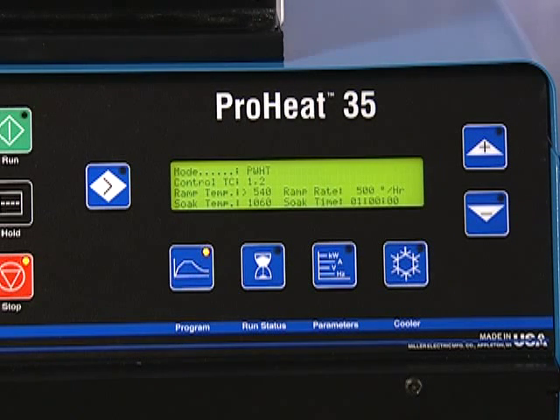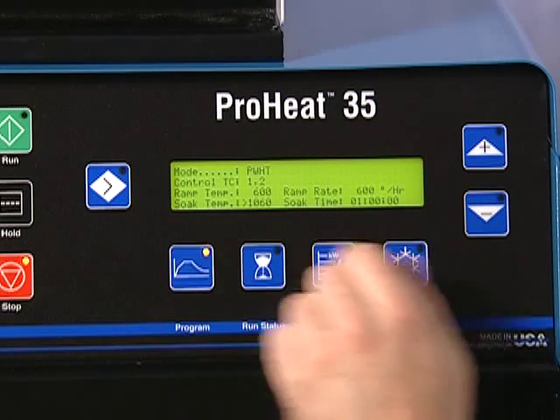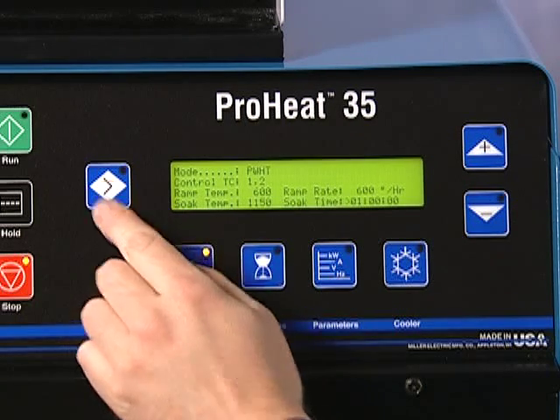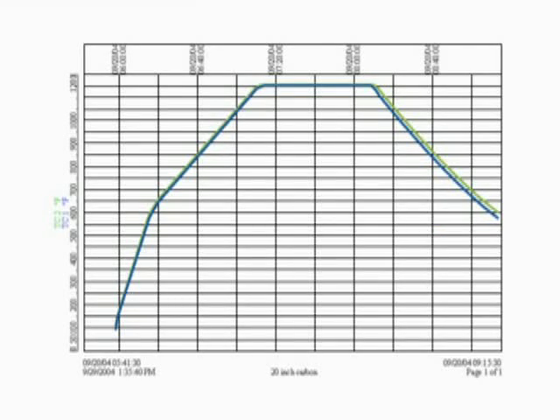Post-weld heat treatment, or stress relieving, is normally an automatic process. You must set targets for controlled heating and controlled cooling, and set ramp rates. Use the Select and Increase/Decrease buttons to set the program. In a simple post-weld heat treatment, the heating and cooling temperature targets and rates are the same. For example, the target temperature for controlled heating and the target temperature for controlled cooling are the same. Similarly, the rate of controlled heating and cooling are the same. The soak temperature and soak time will vary depending on material type and thickness.